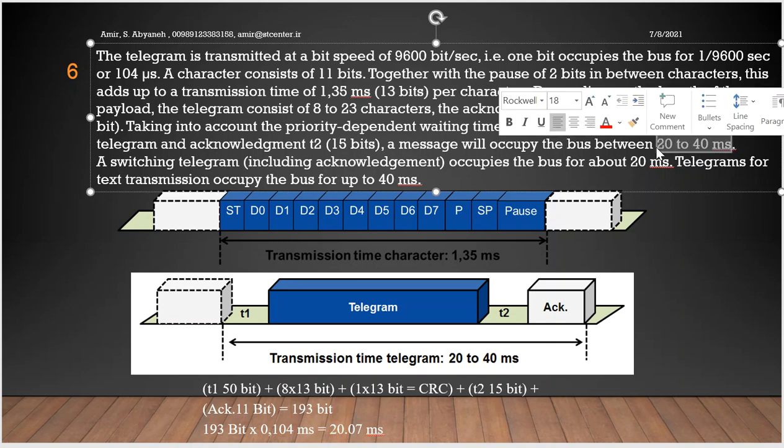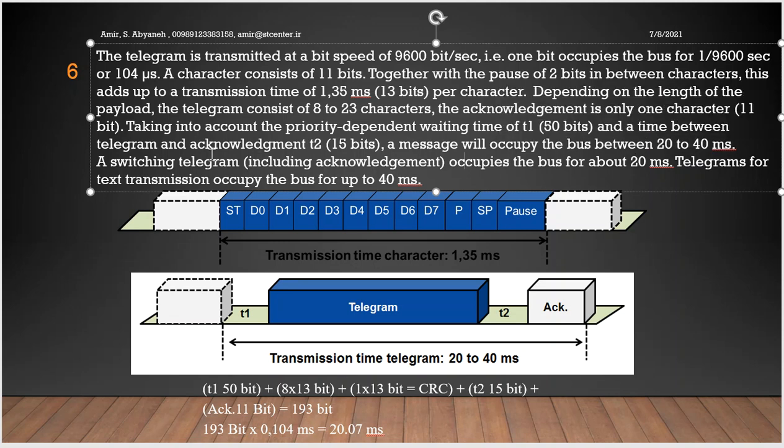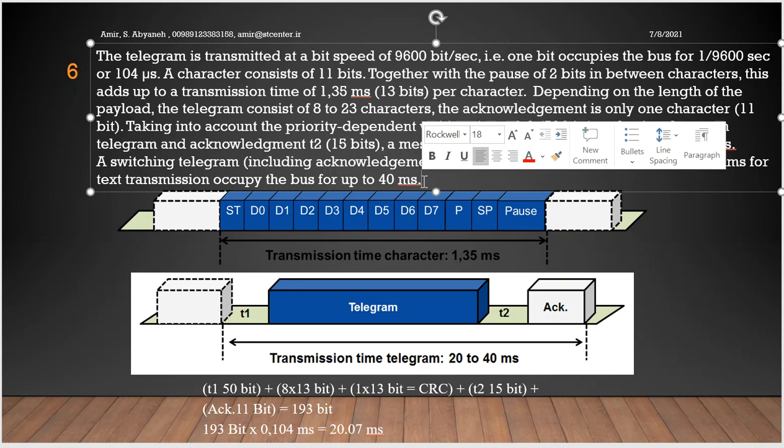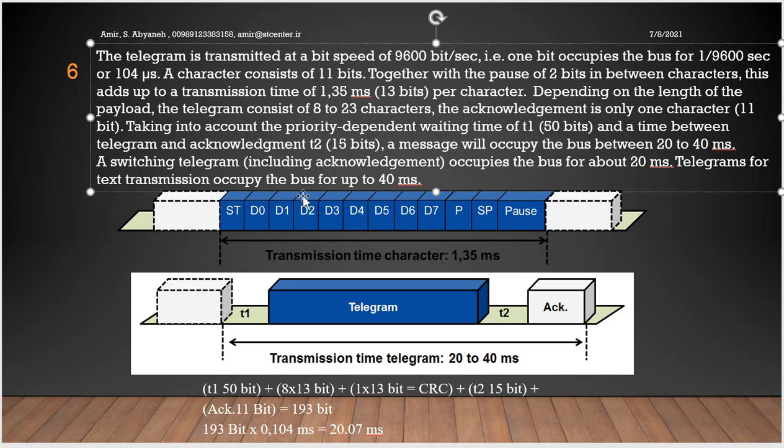A switching telegram including acknowledgement occupies the bus for about 20 milliseconds. Telegram for text transmission occupies the bus for 40 milliseconds. Text transmission, for example in a hotel room, you want to send welcome to the room throughout the KNX bus.